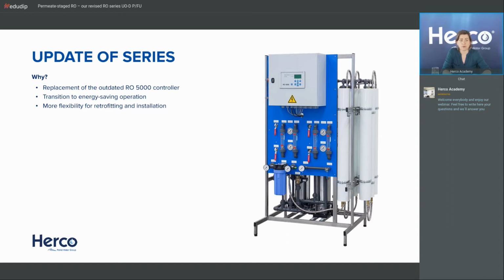It's a good controller, but the thing is, with this controller, you cannot really check all the values. So you cannot check flow rates, you cannot check pressures, you don't have any warnings. You see them visually, you can adjust them, but you don't have really any checks in the controller and any safety measures, let's say. So we wanted to replace the controller.